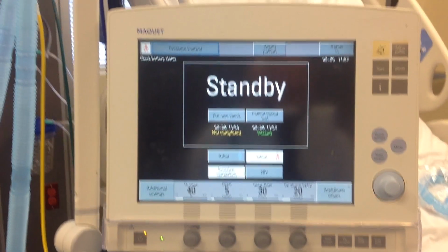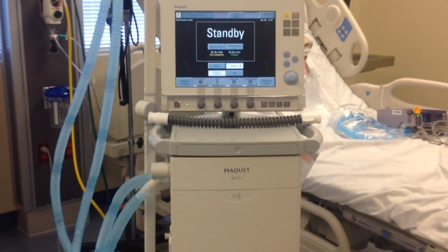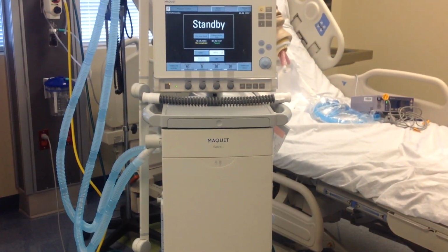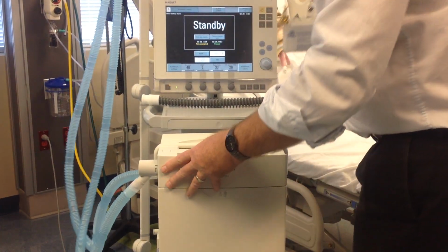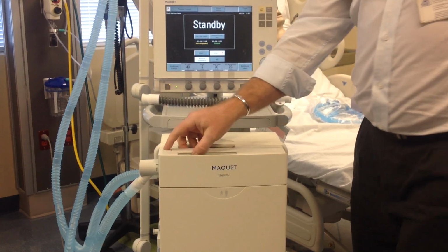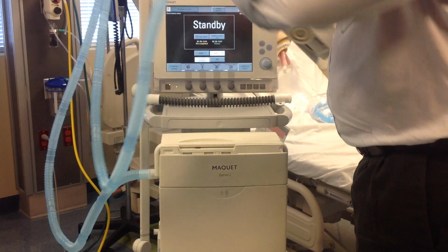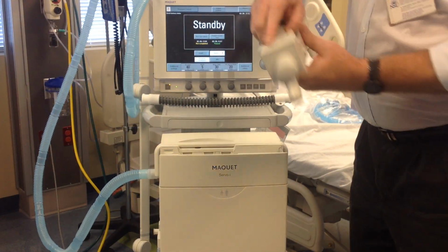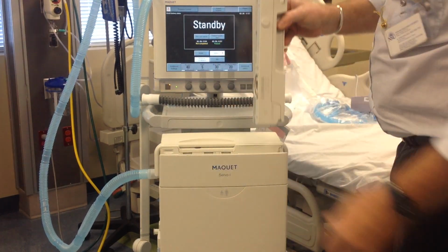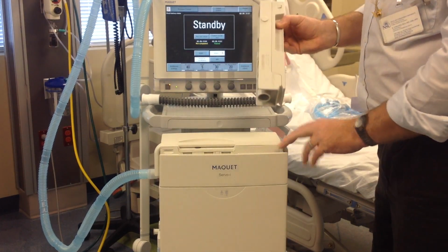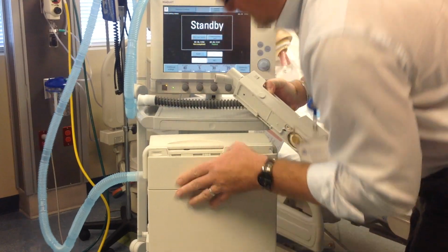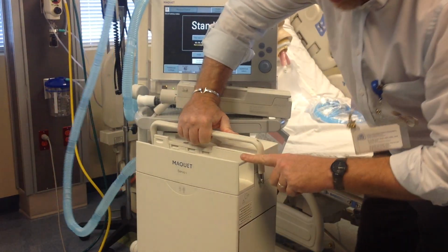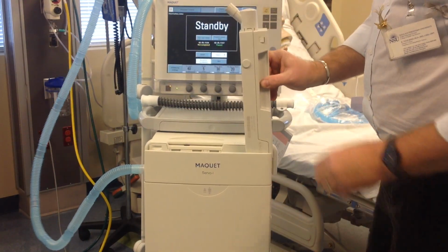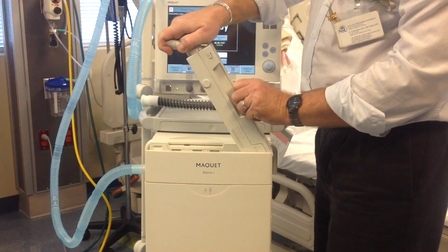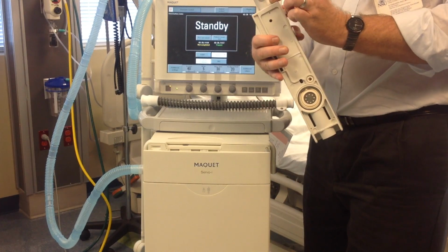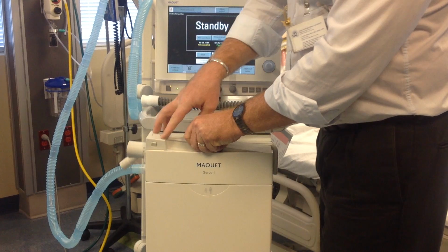One last thing on the setup of the ventilator. I'm going to pull out here. There. This ventilator, you can actually pull this out. Now sometimes, when I'm talking about water, water gets into this cartridge. This is your exhalation cartridge. You push down, lift up. I'm going to take the circuit off. The release button is right here on top. When you put it in, this notch goes onto a bar right here. The bar right there. And when you put it on and you push here, do not push down on this. Again, if you push here, you can get microfractures and your ventilator will not pass the pressure test. And you push it down until it clicks.